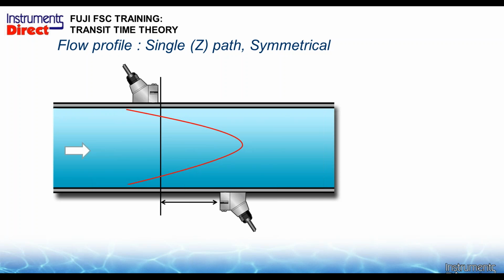So the neat thing about the ultrasonic transit time flow meter is it's a big math equation, and the flow meter does all the math for you. You just need to put in a couple of the basic variables. So in this case, if I put in the pipe size, the pipe material, and the process liquid, the device will calculate that this sensor should be here, and this sensor should be here, and the flow profile will look just like this if I had my proper straight run of pipe. Turn on the button, signal goes from here to here, everything's perfect, your optimum performance.